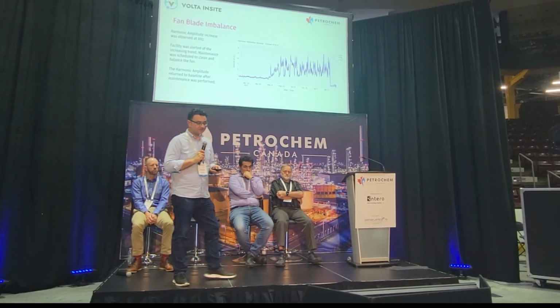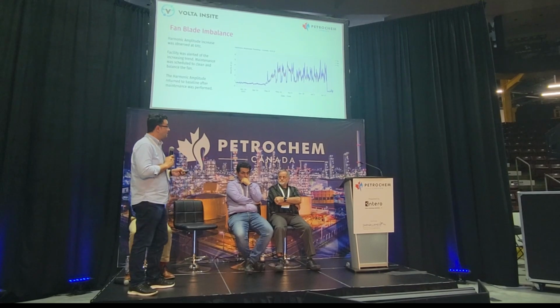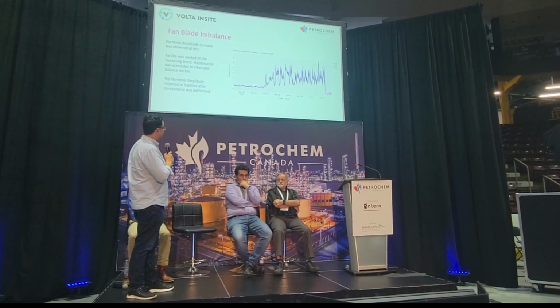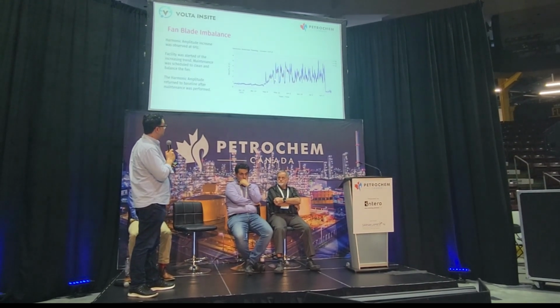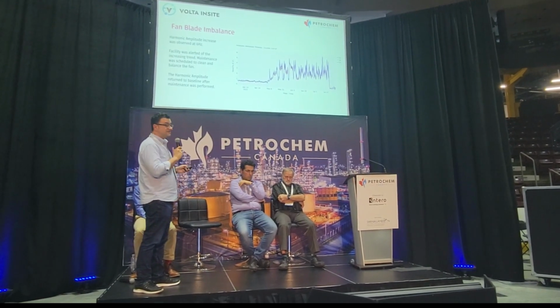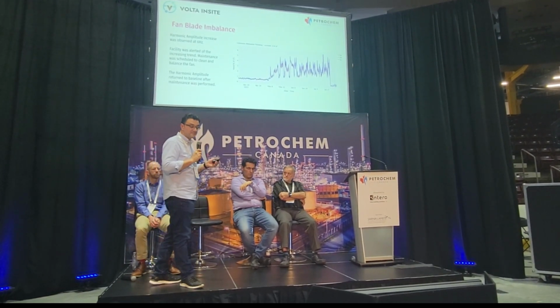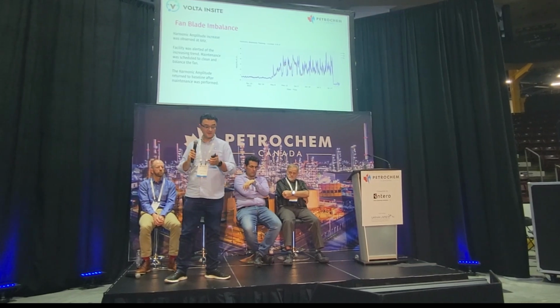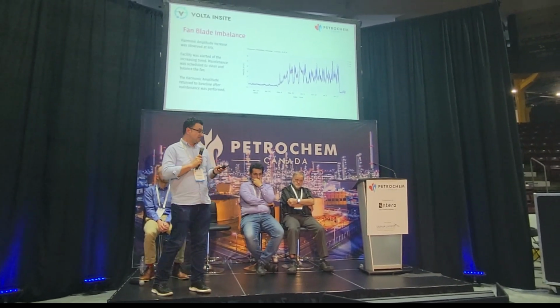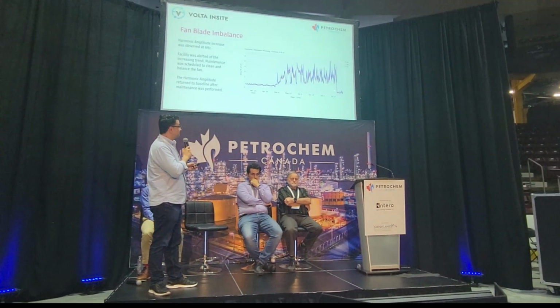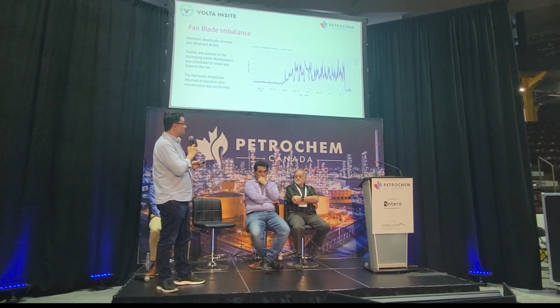Here's another example of a fan. In this case, we had baselined this particular harmonic. We start jumping all around. Turns out that the fan itself had a lot of debris built up on its blades. They scheduled maintenance, they took the fan down, they cleaned the blades, rebalanced it, and we're back to baseline.